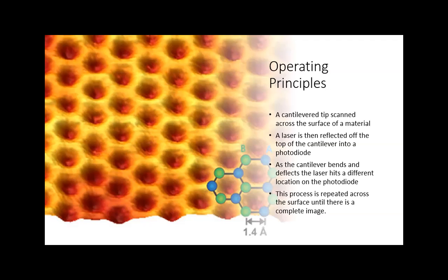Cosmo, do you have another question? Yeah, generally speaking, when you're selecting among the variations of the different contact methodologies for this cantilever mechanism, what sort of factors usually go into one getting selected over the other, whether it be contact, non-contact, or tapping? I think you have to have some expectation of what your surface is going to look like. And you have to know the chemical and magnetic properties of your surface, because those can contribute to the forces.